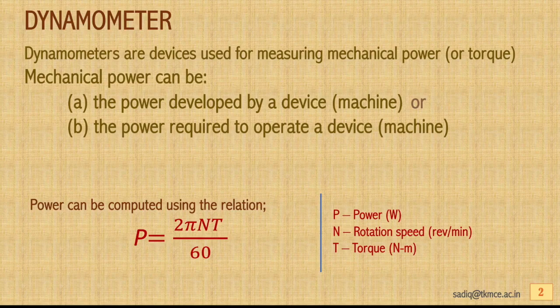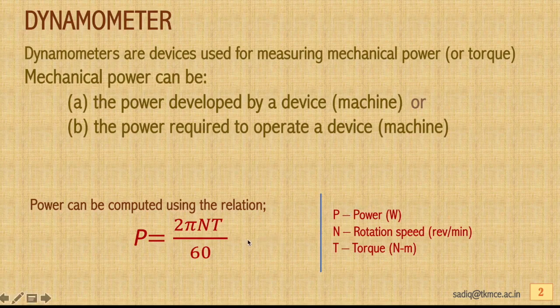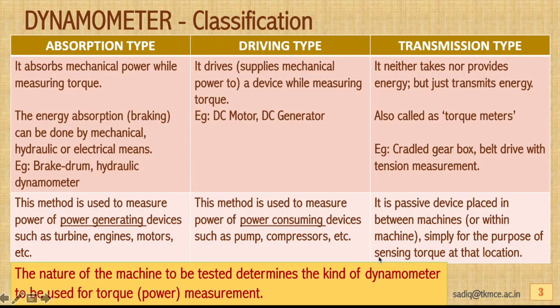Dynamometers are devices used for measuring mechanical power or torque. Mechanical power means the power that can be developed by a device or machine, or the power required to operate a machine. We know that power is a computed parameter based on the equation P = 2πNT, where N is the rotation speed in revolutions per minute and T is the torque in Newton meters.